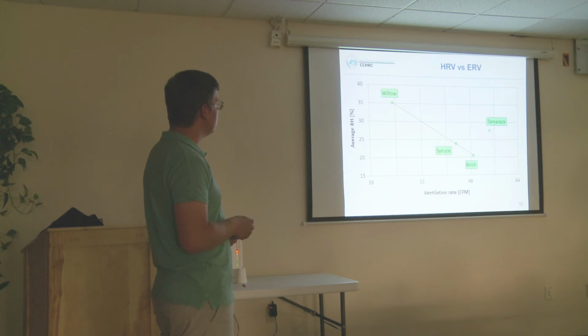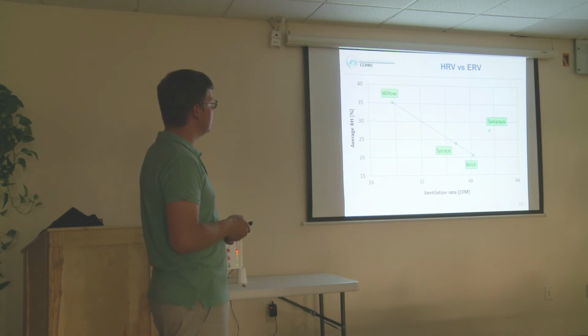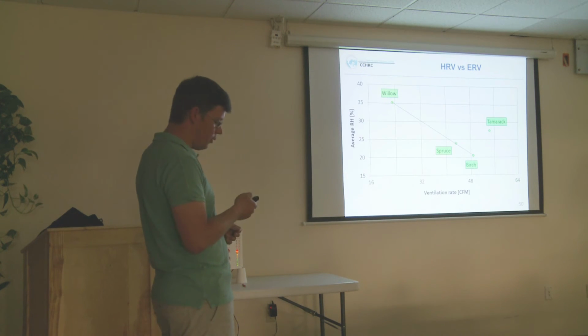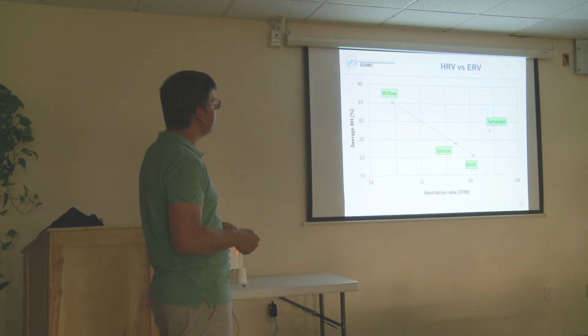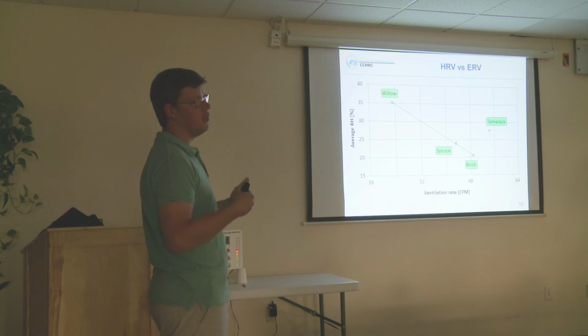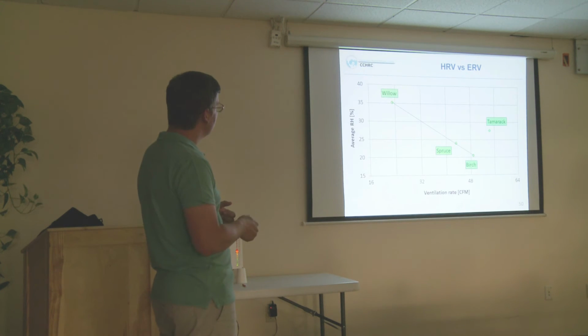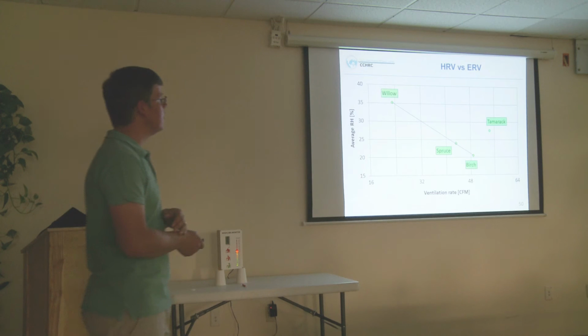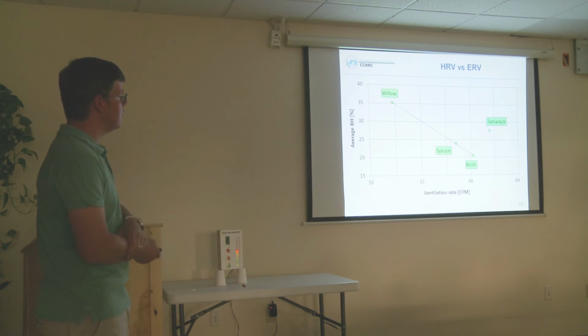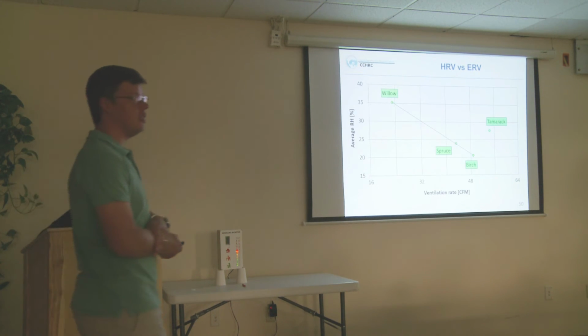The good thing about one of the units was that it has an ERV core, so it allowed for moisture reduction, for moisture transfer. We could clearly see that the more fresh air we bring in, the drier the indoor environment will be. That's not surprising in these three cases, except for this one, which actually has more fresh air coming in, but the relative humidity is somewhat higher because of the moisture recovery in the unit.